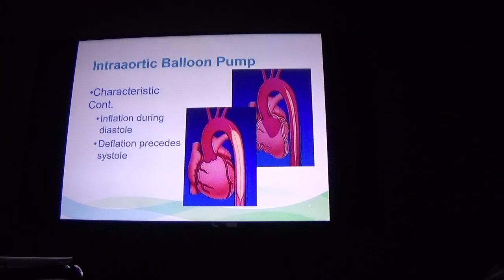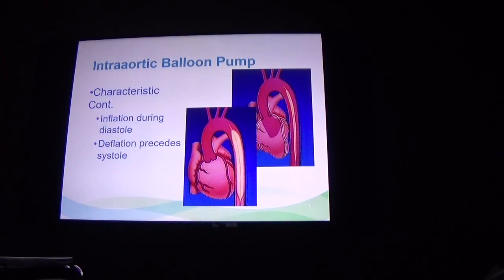So the balloon actually inflates during diastole, so the heart has just got done squeezing and now it's relaxing and filling, and that's when the balloon kicks in and pumps up. That's what's called diastolic augmentation. And then right before systole, it triggers off the R wave of an EKG typically. It will deflate rapidly. So it basically sucks all that helium back out, and your diastolic pressure actually falls much lower than it would without this. So now you have a low diastolic pressure that your heart has to push against. So your heart doesn't actually have to work quite as hard.